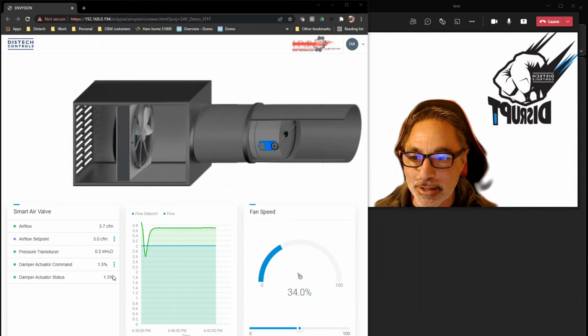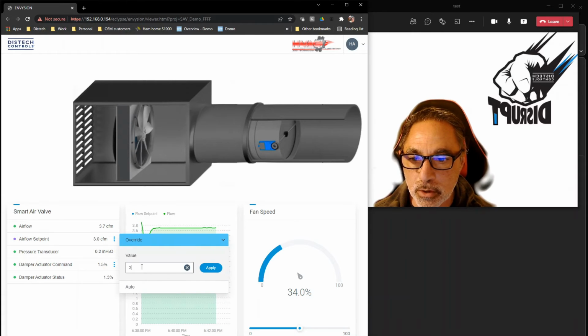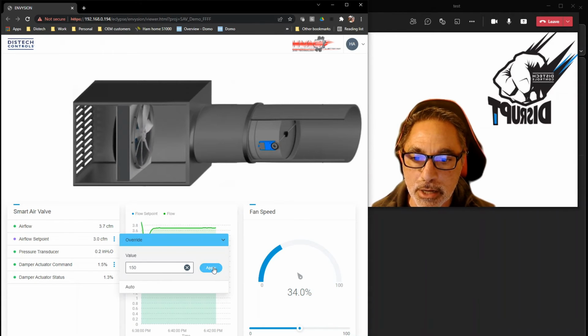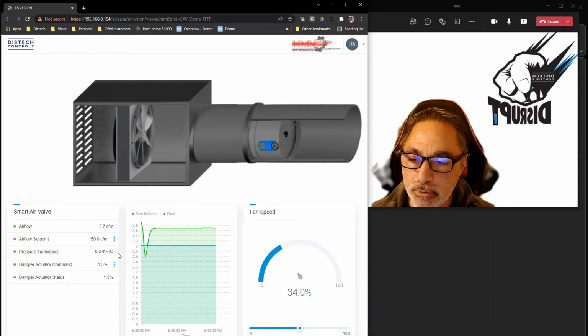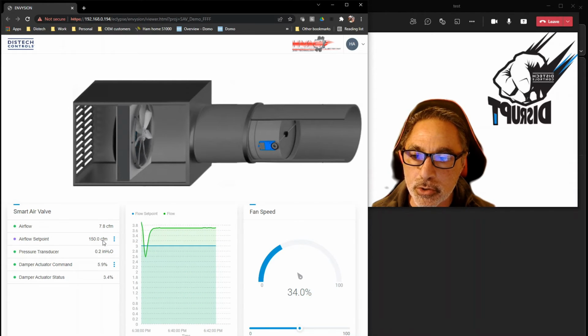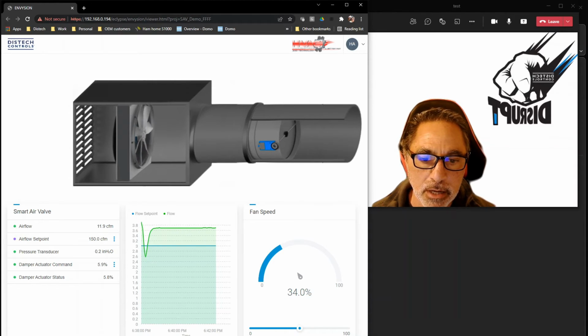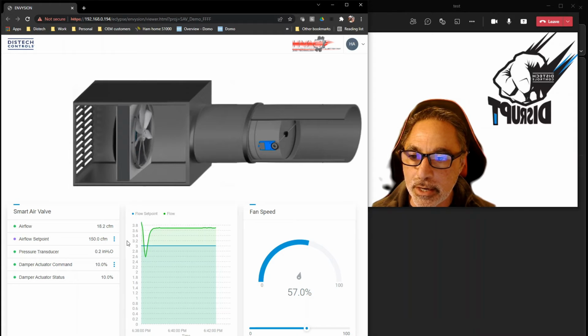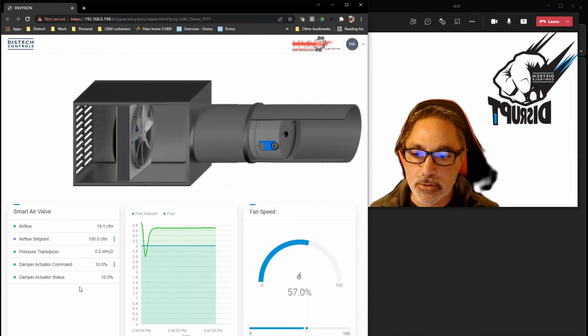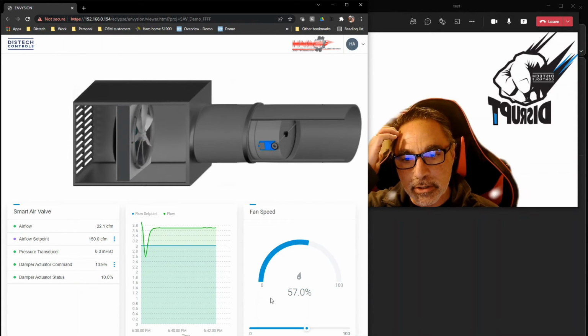but I do want to make sure you understand this is not magic. I'm going to go ahead and change this to a value that maybe my fan could get to. So let's say about 150 CFM. I want to tell it to go at 150 CFM. So what it should do now, as you can see, is start increasing the CFM immediately. I'm going to speed up my fan to try to get the speed as fast as we can to get to that 150 CFM.